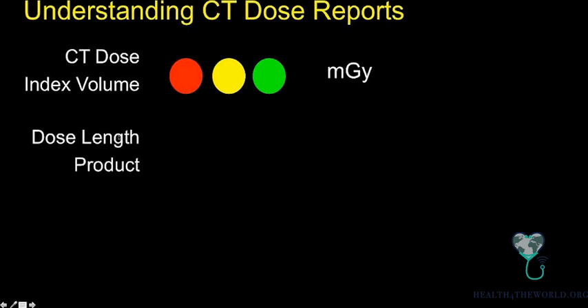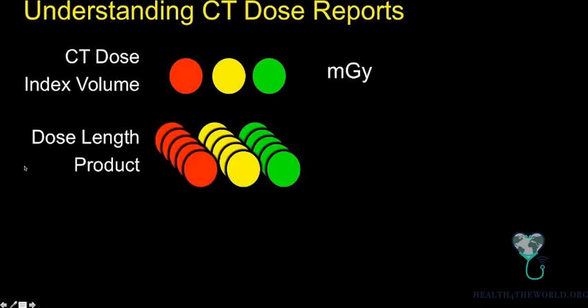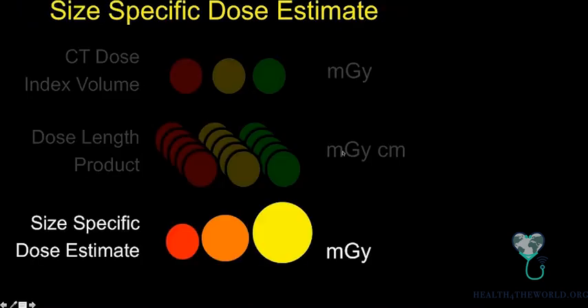The next most important value — and perhaps the most important unit to take away from this lecture — is the Dose Length Product (DLP). It represents how many slices were obtained multiplied by the dose per slice. The unit is milligray times centimeter. You can almost think of it as a volume: it takes the slice hotness and multiplies by a distance to give you a number that is the most meaningful in terms of overall exposure for that patient for that study. The longer or hotter the scan, the higher the DLP.